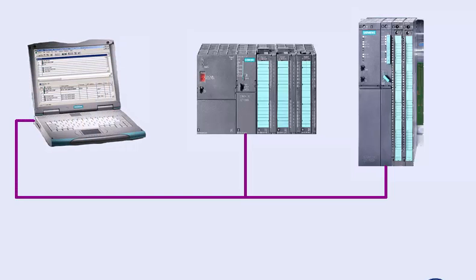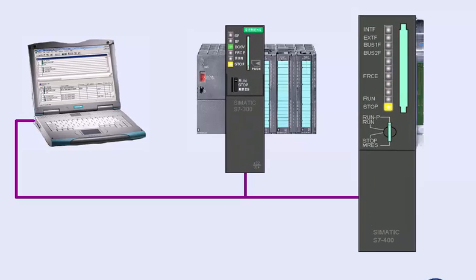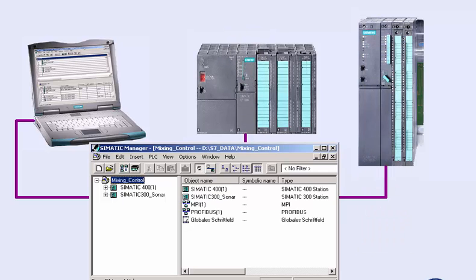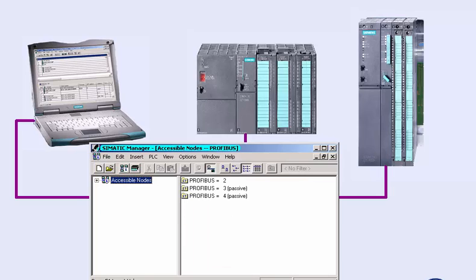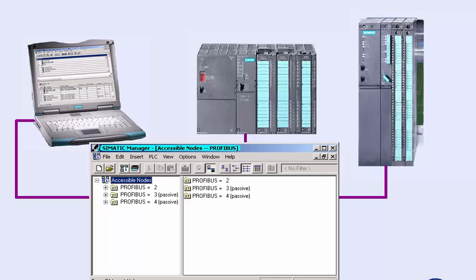The programming device is connected at the PROFIBUS and the PROFIBUS station addresses of the automation devices have been set according to the plant configuration. After switching on the supply voltage, the LEDs at the front of the CPU indicate the operating mode — the power is on and the CPU is in stop mode. The accessible nodes function of the SIMATIC manager shows us all the modules accessible at the bus system and their addresses.